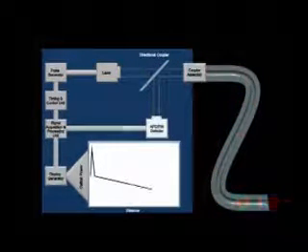A pigtailed laser is routed through an optical coupler to the OTDR front panel connector.